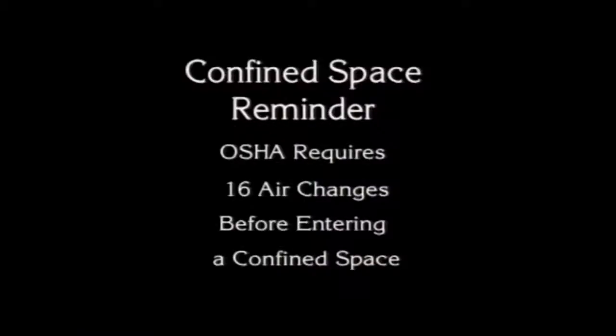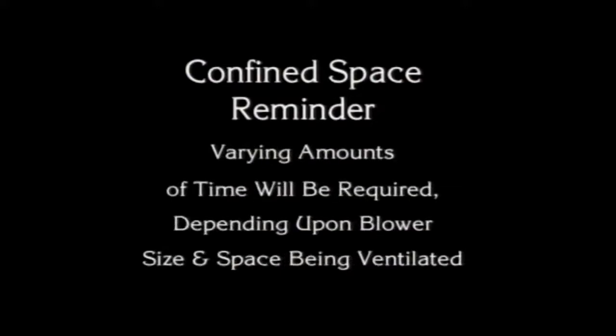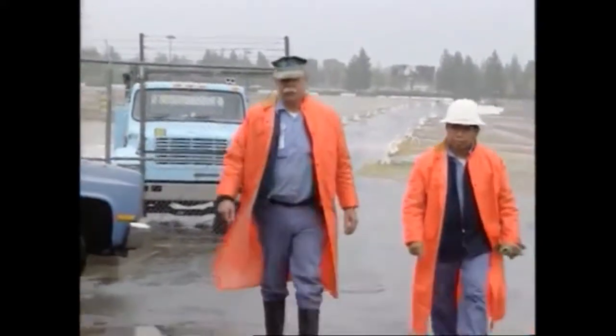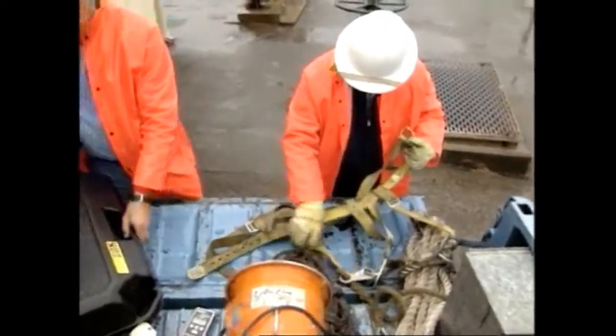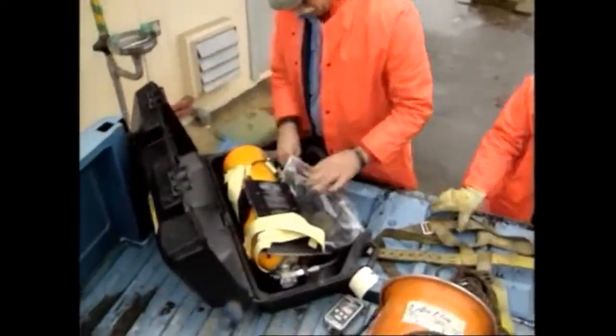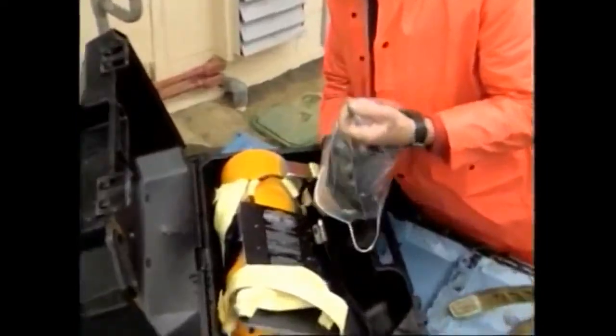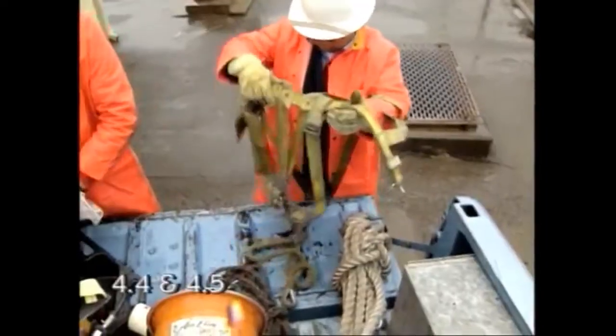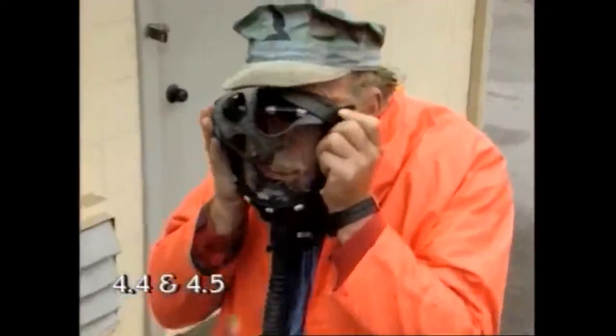Here's a reminder. OSHA requires 16 air changes before entering a confined space, and to do that, varying amounts of time will be required depending on the blower size and space being ventilated. If the station must be entered to correct a serious problem, additional help must be requested. You will also need a safety harness and self-contained breathing equipment for re-entry to the station under hazardous conditions. All applicable confined space entry procedures must be followed in these situations.